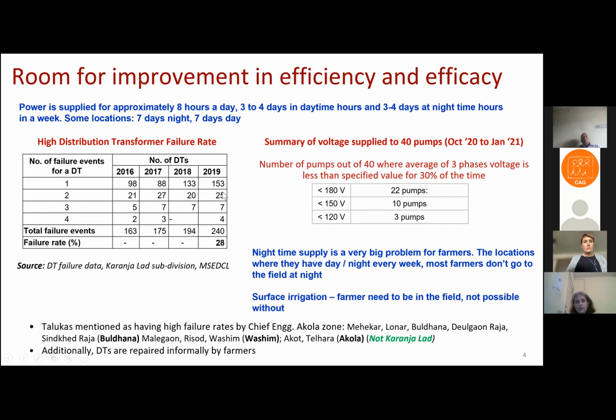The right side shows voltages, and we metered 40 pumps starting from October 20 till the present—this is data till Jan 21. Out of the 40 pumps, 22 had average voltage of less than 180 volts for 30% of the time. So very high. In fact, many pumps now in rural areas are set up such that they operate well even at low voltages.